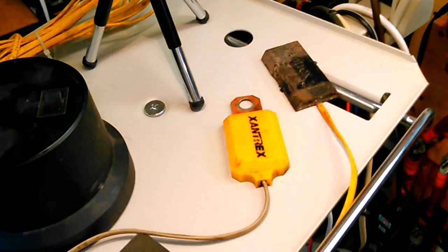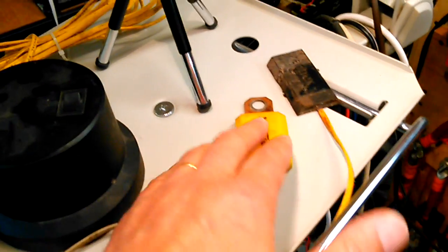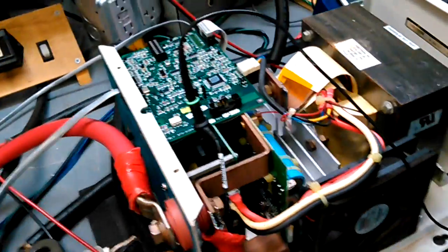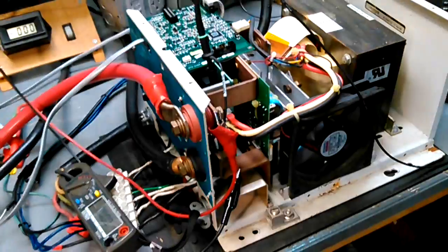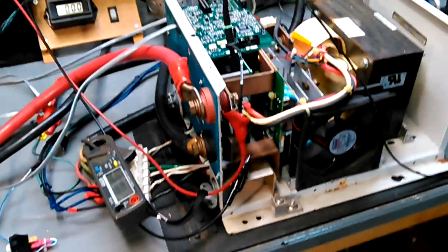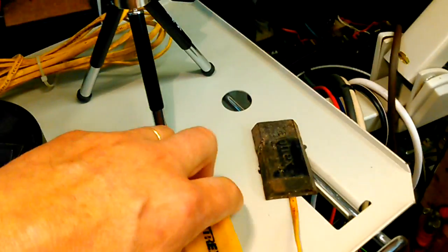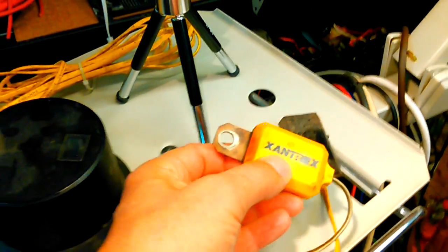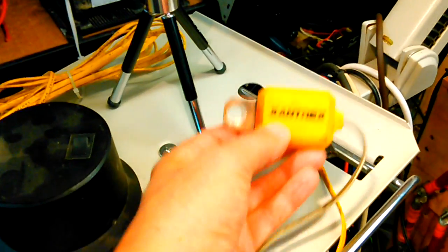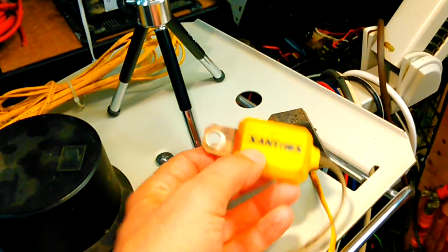These are thermocouples that report the temperature value to the main unit, and it will alter the charge cycle to help prevent overcharging the batteries on hot days and undercharging the batteries on cold days. So it's just an optional feature. You don't have to have it to run it, but it helps to increase the life of your batteries.